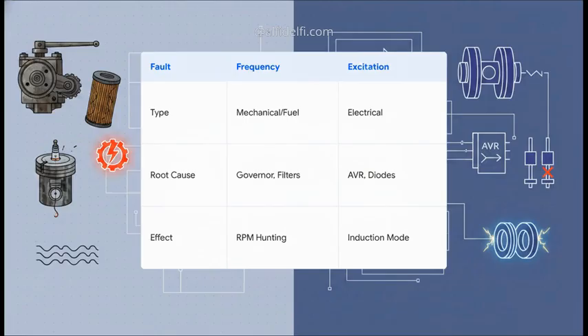Loss of excitation, however, that is purely an electrical fault. The generator has slipped into induction mode because the DC supply to the rotor has completely collapsed. So here, you really need to diagnose the automatic voltage regulator, the AVR. You'll be looking for a rotating rectifier diode failure, a rotor earth fault, or maybe slip ring arcing.